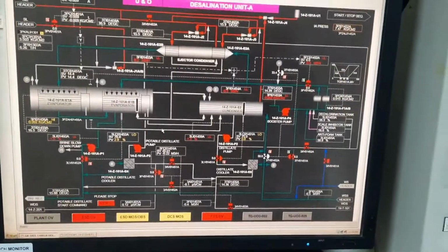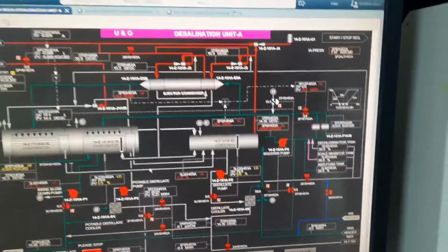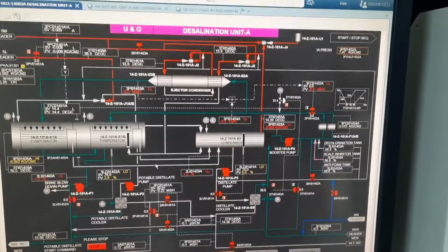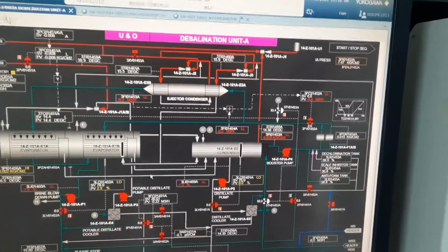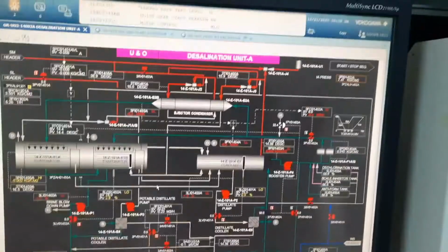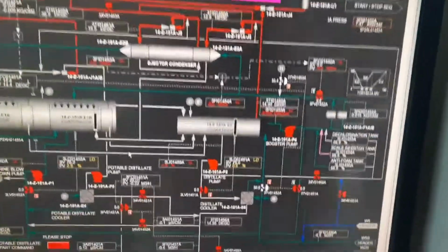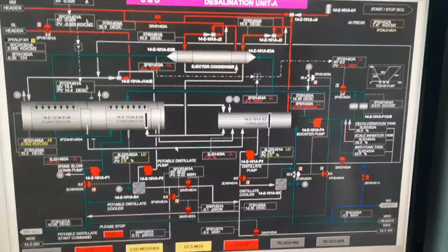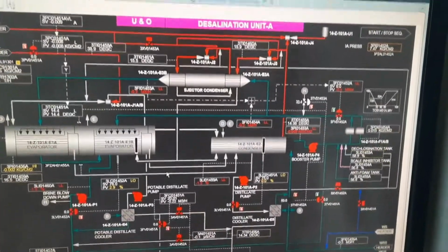Finally, when the acid cleaning is finished, we will remove all the water to the outfall, break the vacuum two times, and then do one rinsing. A 24-hour rinsing is better. Rinsing means water circulation, and after that we will start EDTA cleaning to remove calcium sulfate, because during the hydrochloric acid cleaning most of the calcium carbonate is removed, but calcium sulfate is still remaining.